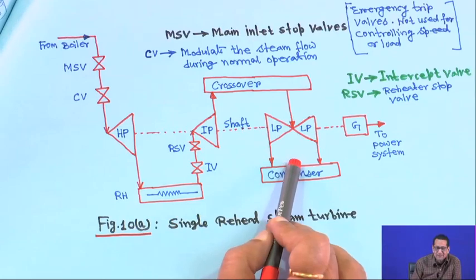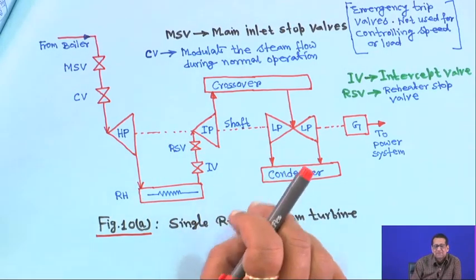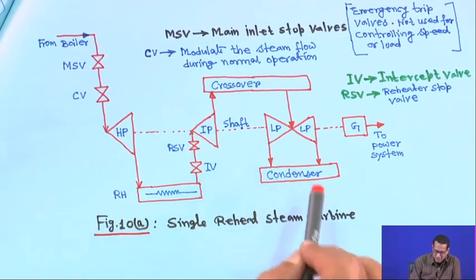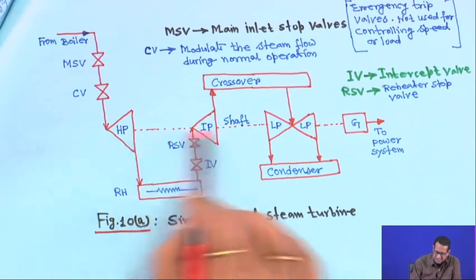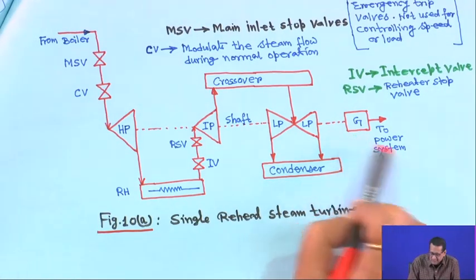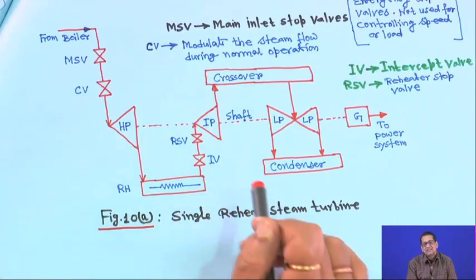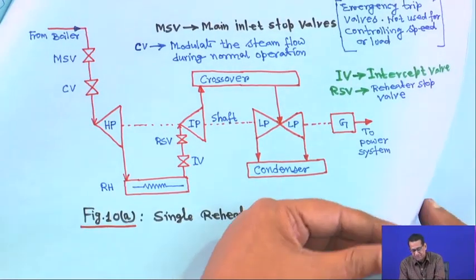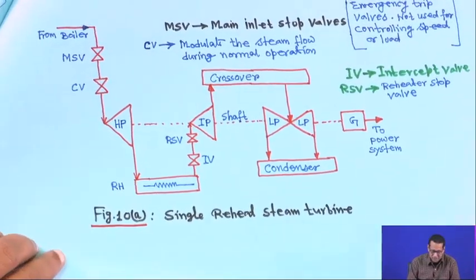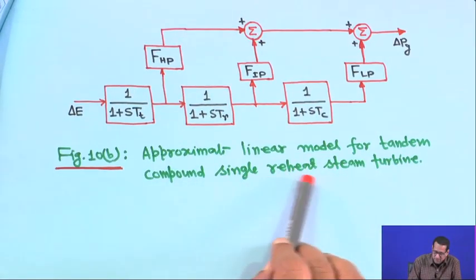From this, we must make the block diagram or control system representation. The key point is that a delay is associated with each section, and every section — high pressure, intermediate pressure, and low pressure — generates some fraction of the total power. We assume a lossless turbine, so total power fractions sum to 1. This gives an approximate linear model for the tandem compound single reheat steam turbine.